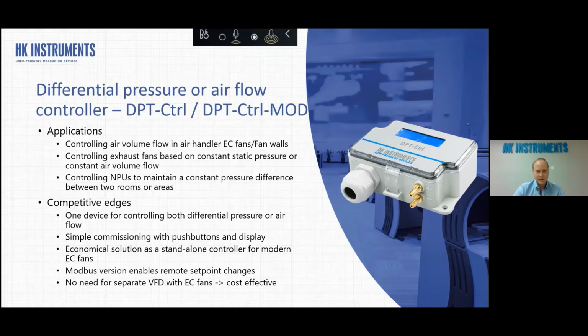Or one special application is these negative pressure units. If you want to maintain a constant pressure between 2 different rooms, you can use this NPU to suck the air, and you can control the pressurizing unit by using this device.